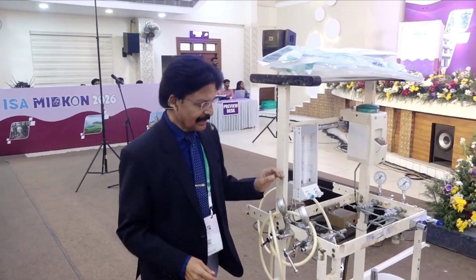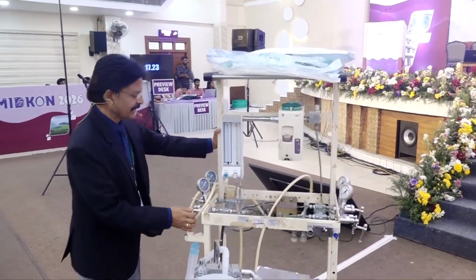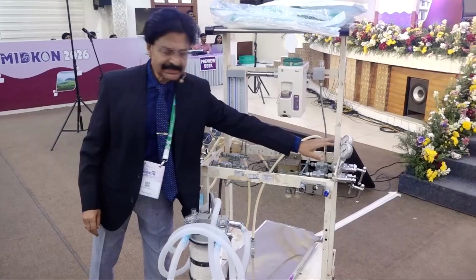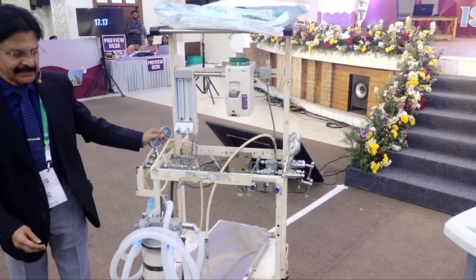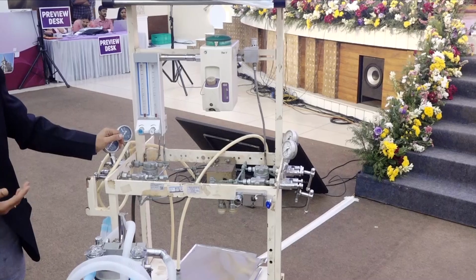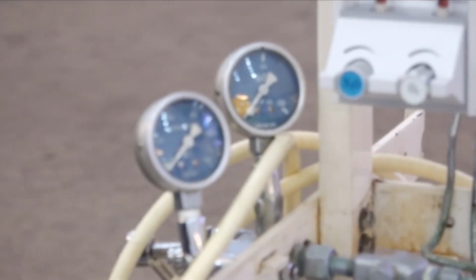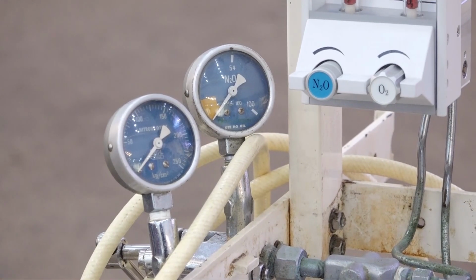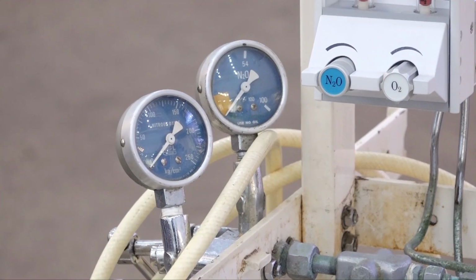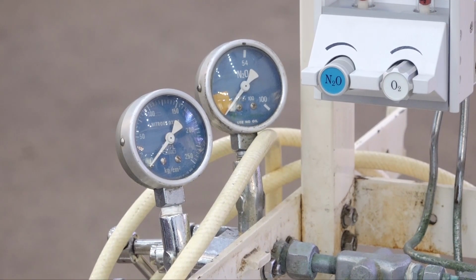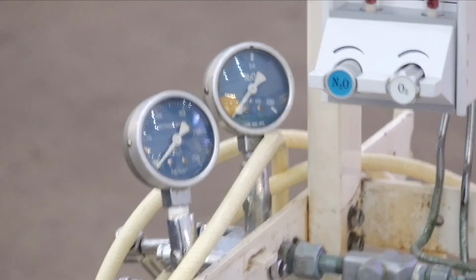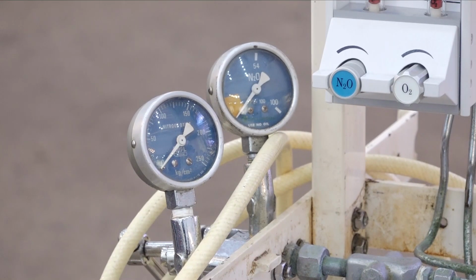And coming to the pressure gauges. You can see these are the pressure gauges for the cylinders. Once you open, you can see the indicator moving on the gauge, and these are called Bourdon pressure gauges. They have a C-shaped tube, and once the gases enter the C-shaped tube, it straightens, and the indicator is connected to the tip. That indicator will move over the gauge and give you the pressures. That is what a Bourdon pressure gauge is.